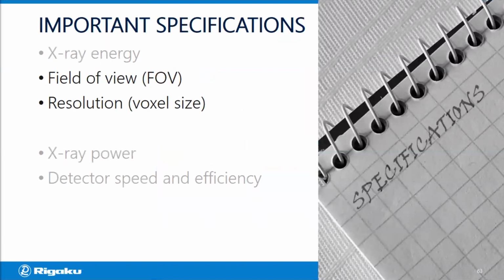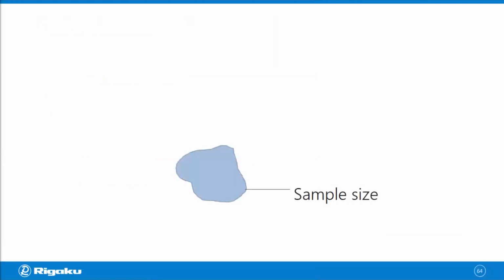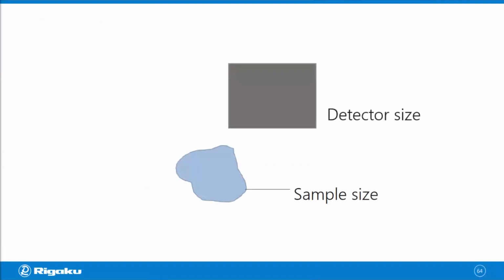Now let's talk about the field of view and the resolution. I would like to talk about those two together because they're related. So let's say that this is your sample, thus this is your sample size. Then if you have a detector here and X-rays go through the sample like this, then this rectangular area is your field of view, or FOV. This is the area that gets projected on the detector. And as you can see, the FOV is not necessarily the same thing as the sample size. The FOV can be either smaller or larger than the sample size.